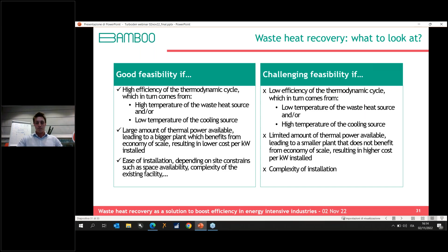On the other hand, the feasibility is challenging if the efficiency of the thermodynamic cycle is low, so if the temperature of your heat source is low, or if the ambient temperature is too high. Then it will result in a very low efficiency cycle, and so a high specific cost per kilowatt produced, and also, of course, complexity of installation. So if the space available is very strict and it's very complex to install the unit, it will be a problem, since the unit is big and typically there is nothing that you can do to fit the unit in a small place.